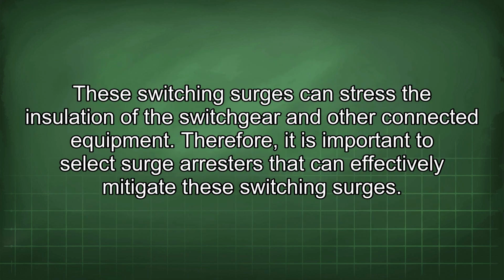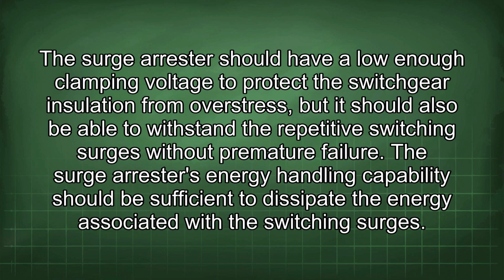These switching surges can stress the insulation of the switchgear and other connected equipment. Therefore, it is important to select surge arrestors that can effectively mitigate these switching surges. The surge arrestor should have a low enough clamping voltage to protect the switchgear insulation from overstress, but it should also be able to withstand the repetitive switching surges without premature failure. The surge arrestor's energy handling capability should be sufficient to dissipate the energy associated with the switching surges.